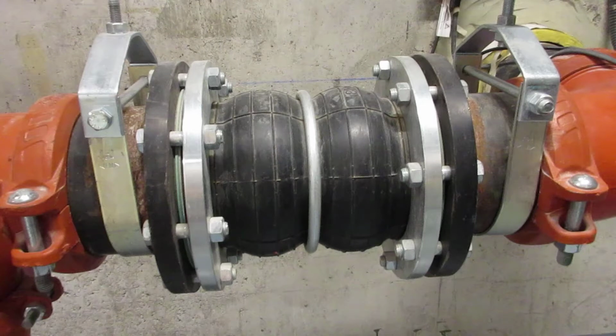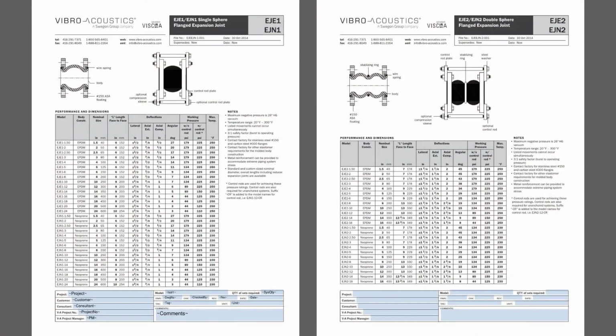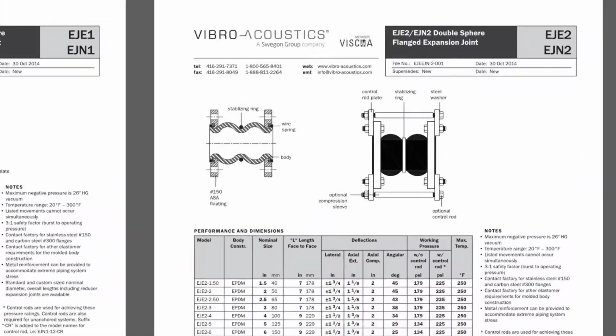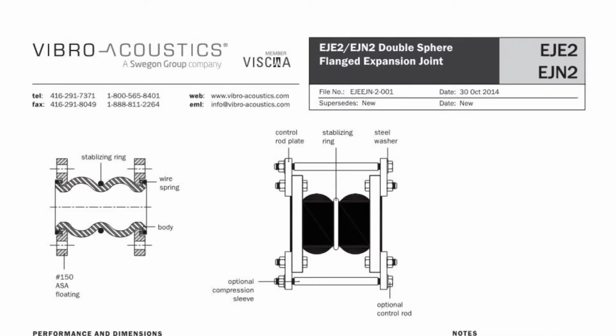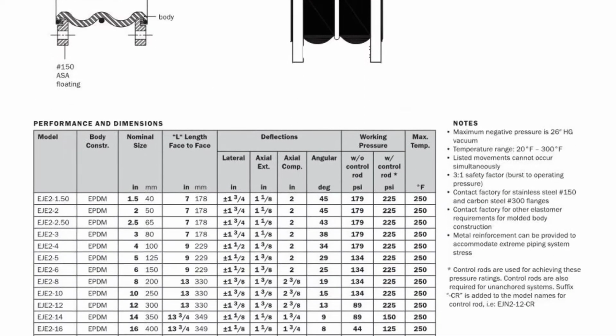We'll pause here and take a look now at the data sheet and installation instructions for these flanged expansion joints. Flanged expansion joints are used as flexible connectors in piping and come in two primary configurations, single sphere and double sphere, and two primary materials, EPDM and neoprene, though other elastomers are available. In addition, these two data sheets also show the common accessory known as control rods. The expansion joint we just looked at is a double sphere neoprene type, and since it didn't have the control rods, we'll hide those for now and discuss them later.